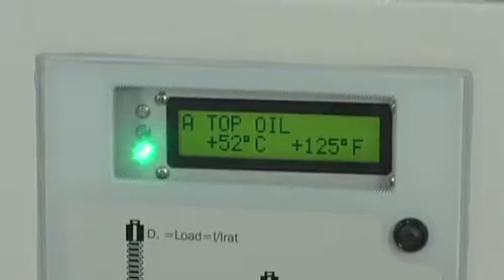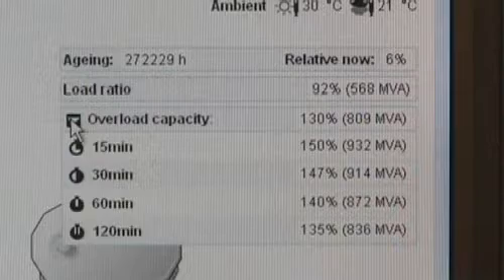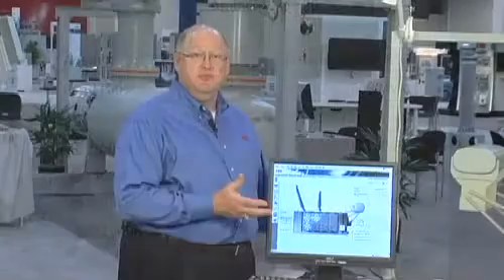Finally, a monitoring system is a wonderful and relatively low-cost idea that lets you keep an eye on your power transformer and make sure it's operating normally. A transformer monitoring system can take a few key parameters — things like bottom oil temperature, top oil temperature, and the load through the bushings — and translate those into real information that helps you understand if your transformer is aging normally and at a predictable rate, or whether it's aging abnormally and you need to take action to lower that aging rate.